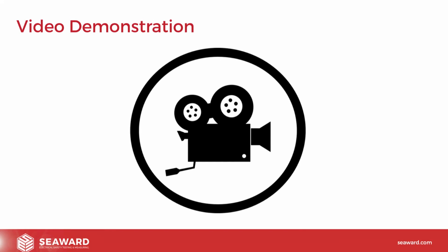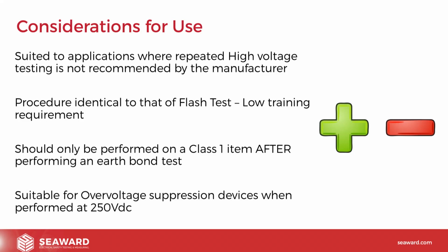Okay, so hopefully the video's proved useful there. Let's move on and discuss the considerations for use when performing an insulation resistance test. So, as we said before, if a manufacturer recommends that a high voltage test isn't suitable, the insulation resistance test could absolutely be the solution to that. In effect, we're only really applying double the mains voltage, and certainly any product on the market should be able to withstand that level of voltage, particularly if it's being powered from a mains supply. As we said, from a training point of view, the procedure is identical to that of flash testing, so it's not too difficult to train your operators in performing these tests.